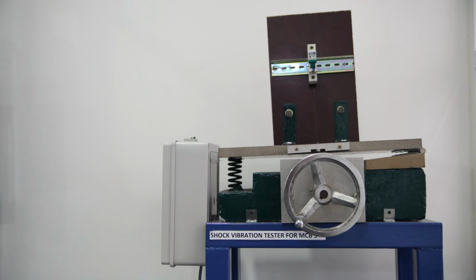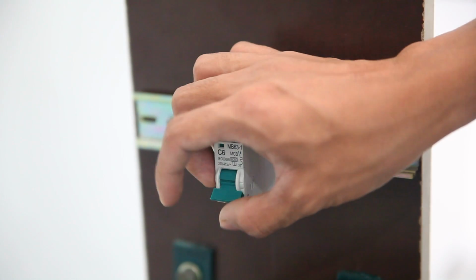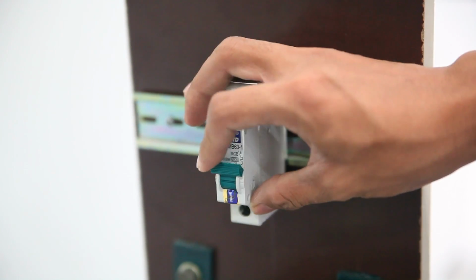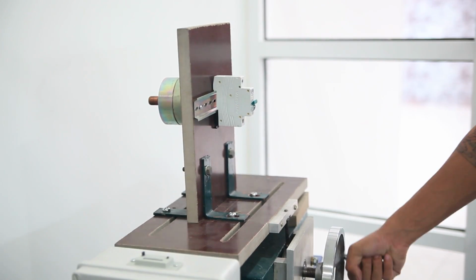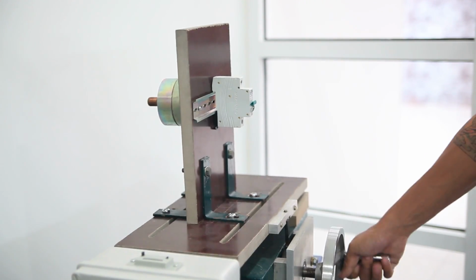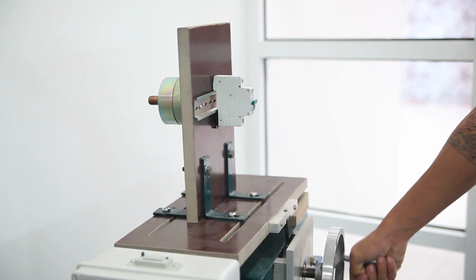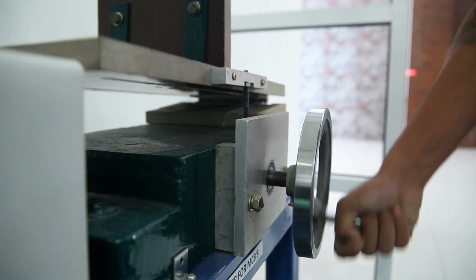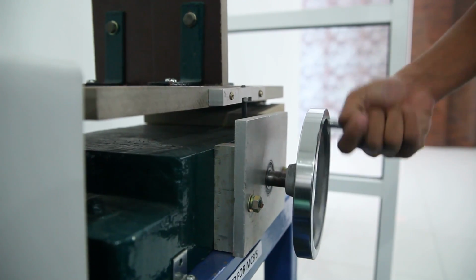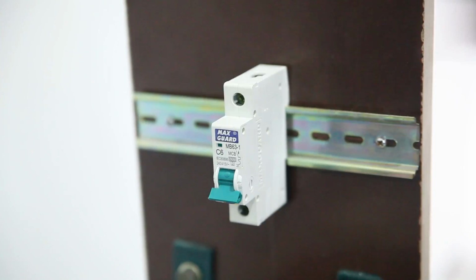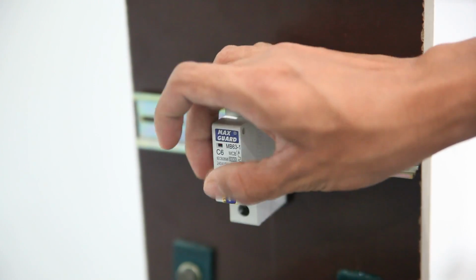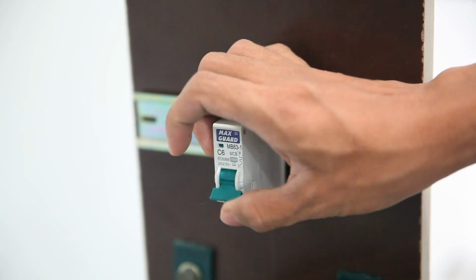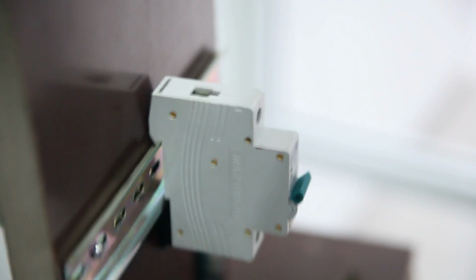Mechanical shock test. The mechanical shock test for MCBs and RCCBs is to check that the mechanical latching integrity of the finished products is able to withstand shocks from vibrations. The test sample is clipped onto the DIN rail, which is mounted on the upright mounting board, followed by turning the rotating handle. After the first cycle of 50 drops, the toggle is switched on and off 3 times to check the mechanical latching is intact before proceeding to an additional 3 cycles.